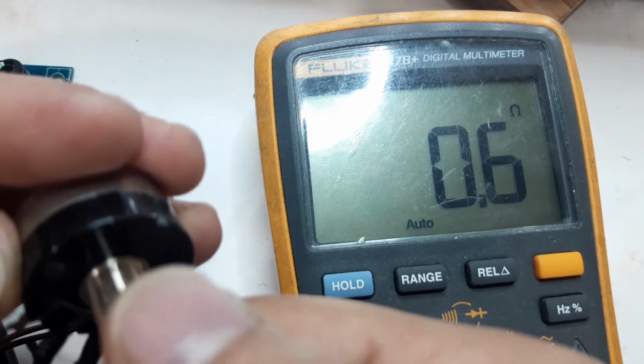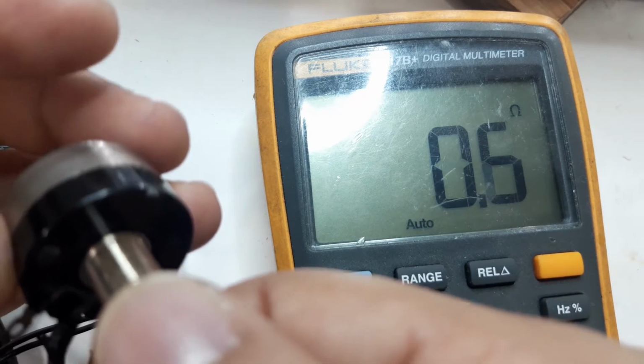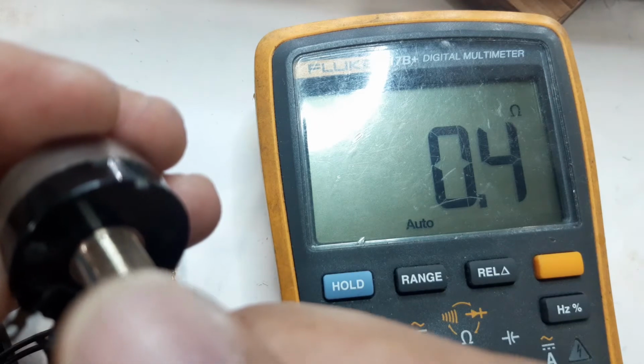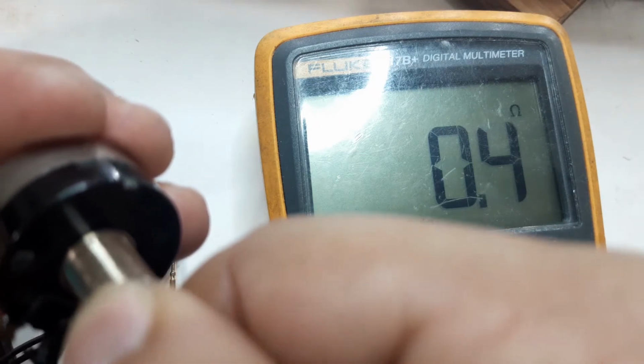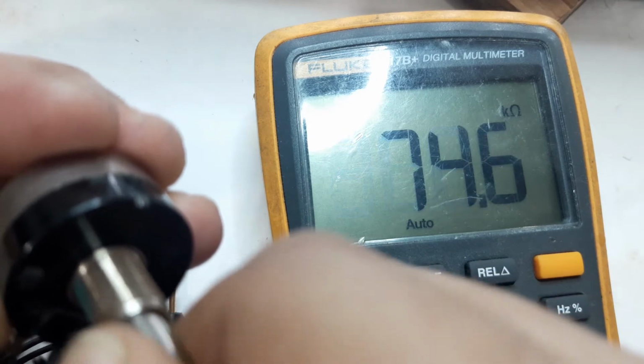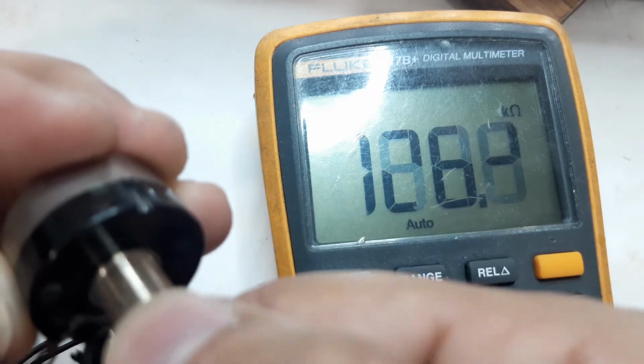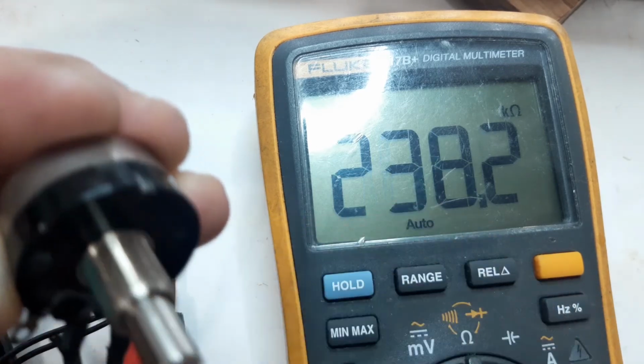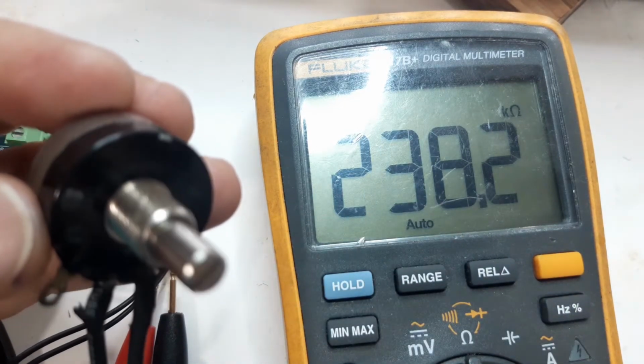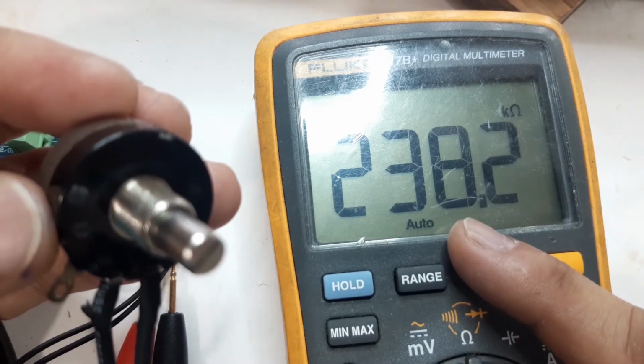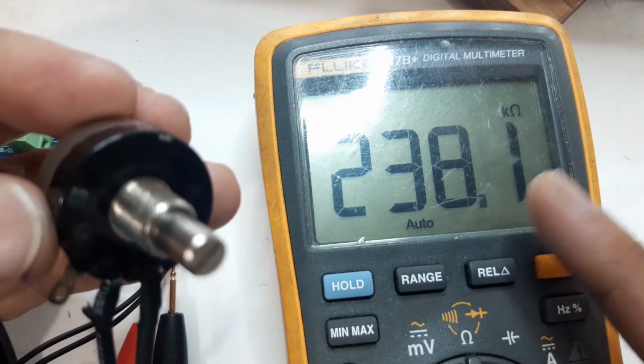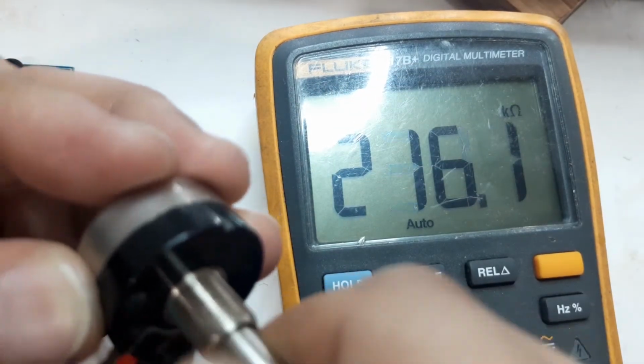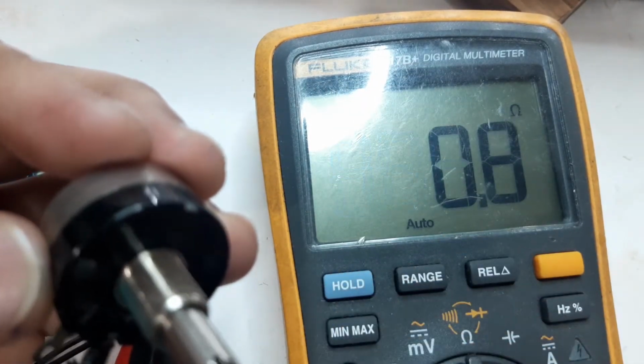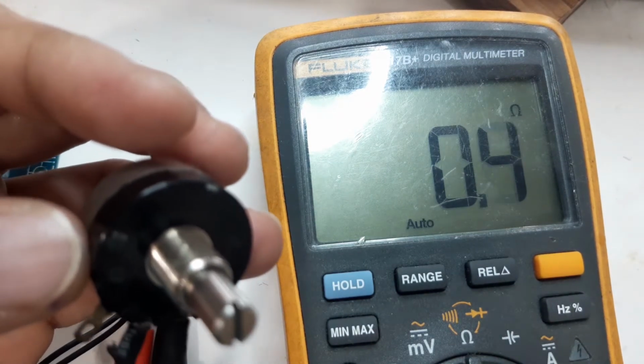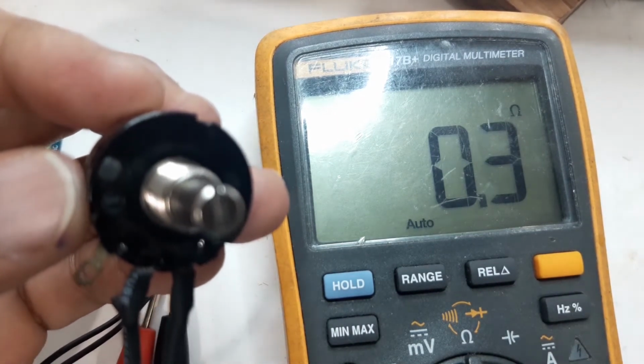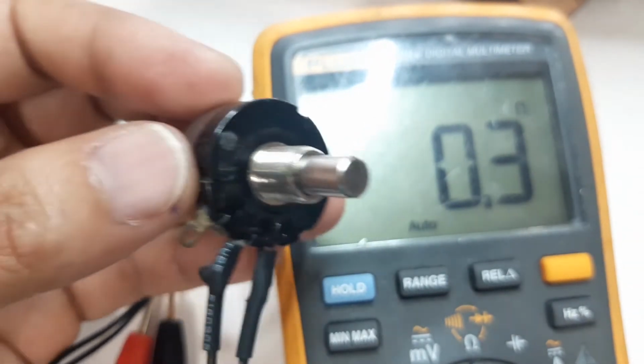Now this is 0. This is the minimum speed of the motor. We have 0.5 ohms, and I will rotate. As you can see, the resistance is increasing. Sorry, by mistake, this is the minimum. The higher the resistance, the slower the speed of the motor, and the lesser the resistance, up to 0, this is the maximum speed. So it means that this potentiometer is working fine.